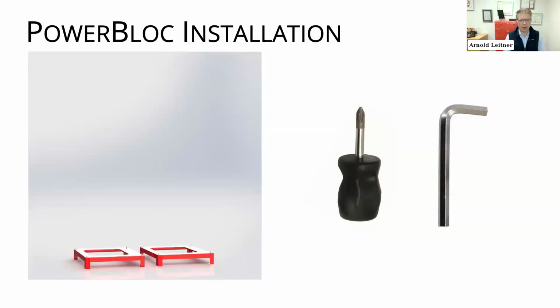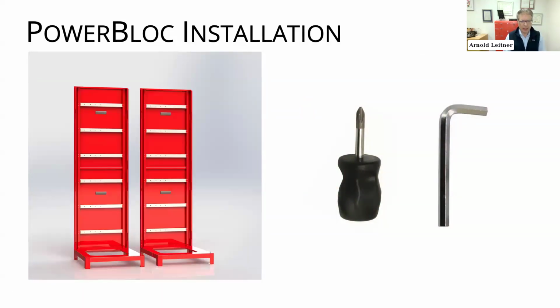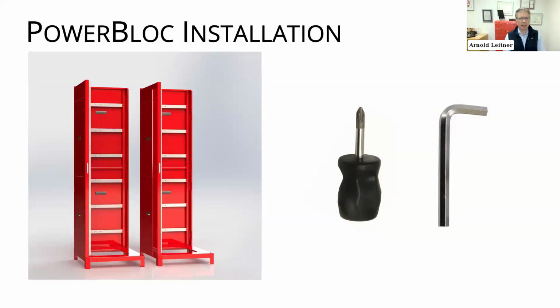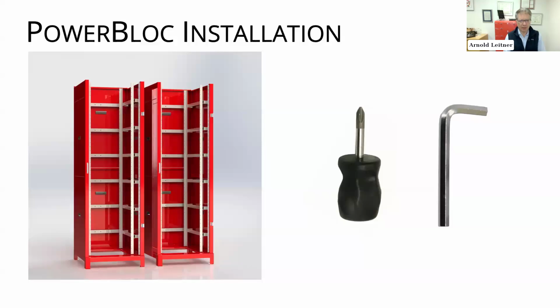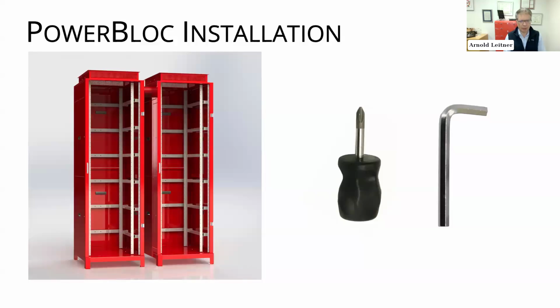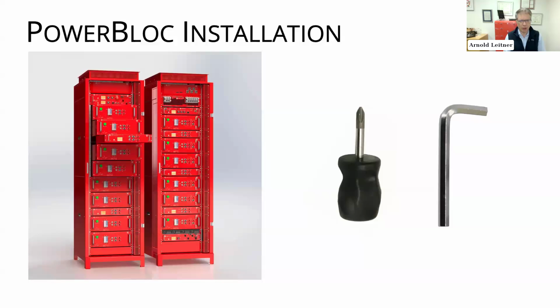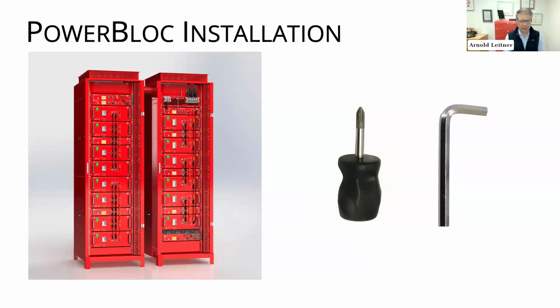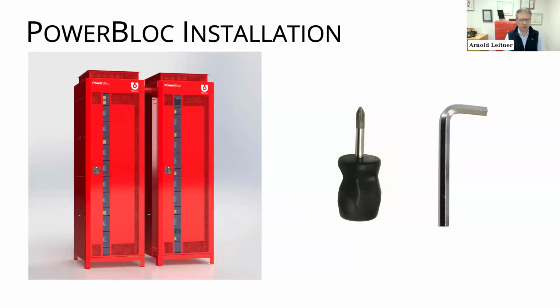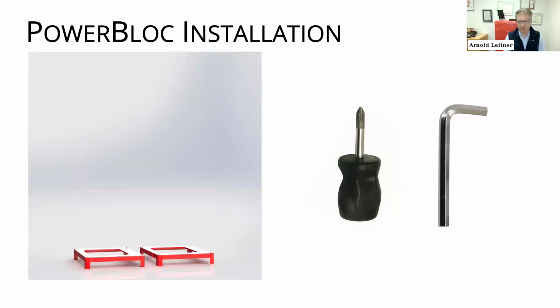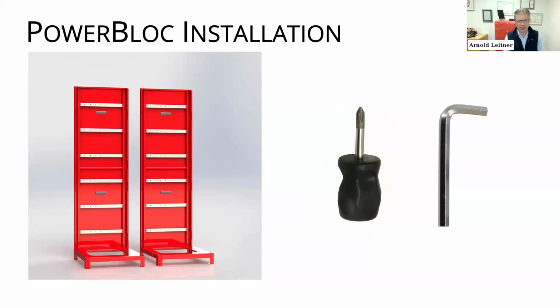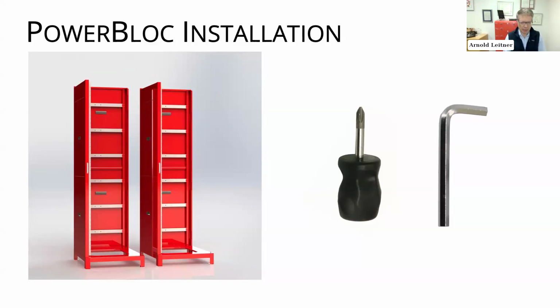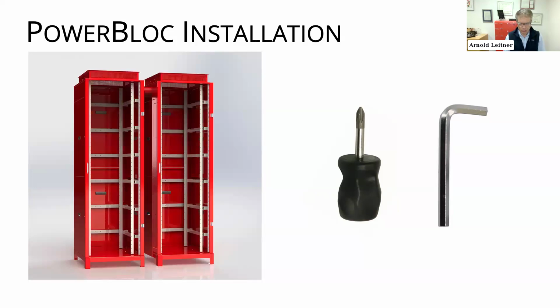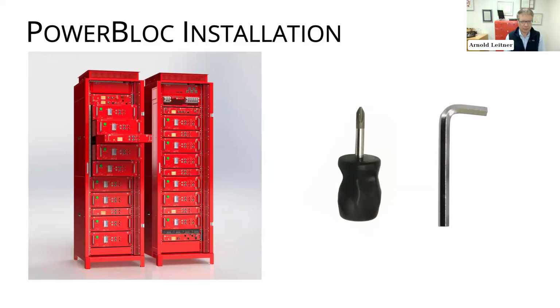Here's a GIF that shows you how the PowerBloc comes together. You just put the bases down, side panels, back panel, the vent hood, very important - we make sure we've got enough aeration. You insert the modules, connect them with click lock connectors for the front, then screw down your modules, and you're done. You only need a Phillips head and an M6 hex wrench to assemble the entire PowerBloc. No more tools required. Everything is click lock.